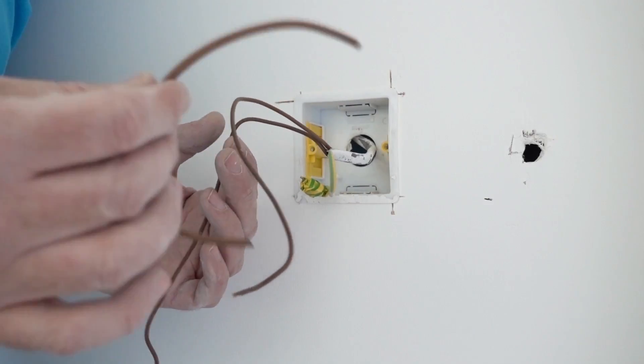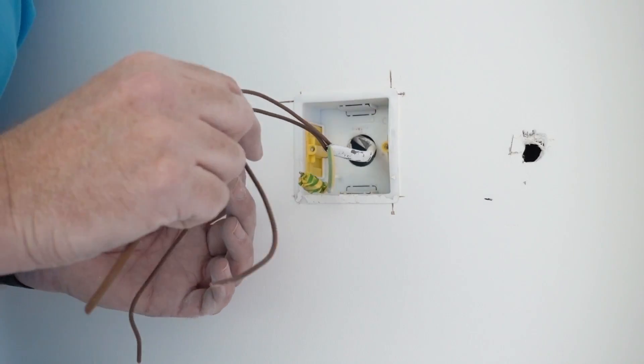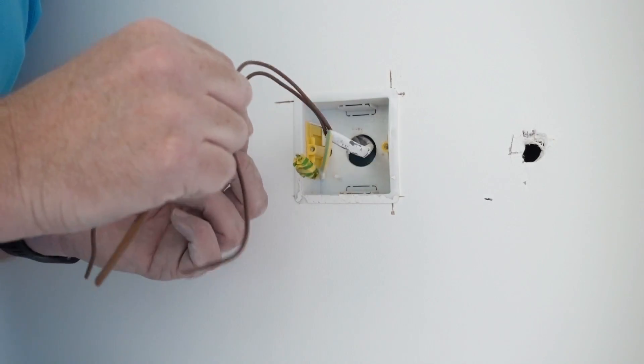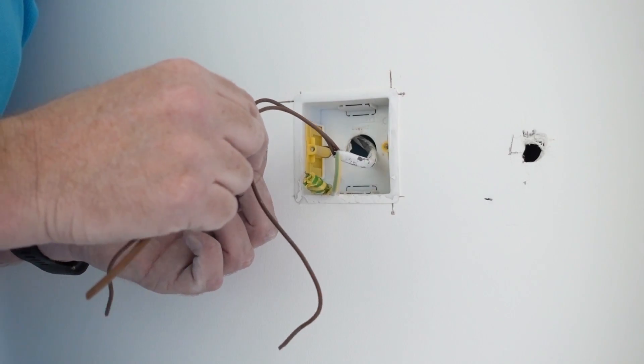Now you might have noticed already that I've got two brown cables. You can do regular twin and earth with a brown and a blue, but if you're doing that you just need to put a bit of brown sleeving on the blue wire to show that both of these are live wires. There's no neutral in here, it's just a switch in the live.